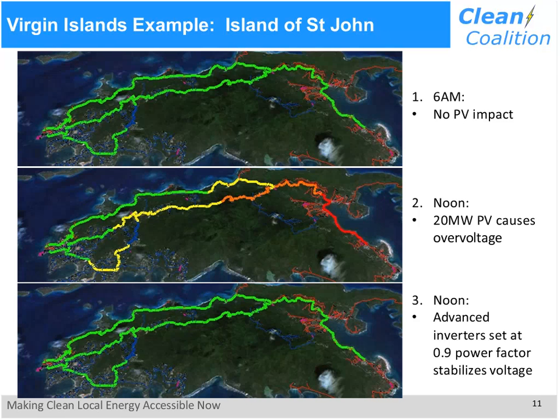The single solution is simply turning on the reactive power provisioning functionality of every inverter sold in the world today, setting it at a 0.9 power factor. That means those inverters can provision some reactive power in addition to regular kilowatt hours, and we end up with a grid that looks exactly the same as it did at 6 a.m. before any solar was being generated.